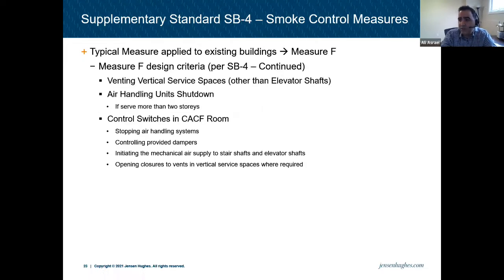So this is basically measure F. Other requirements: if you have other shafts or other vertical service spaces, you may have to pressurize those. Air handling unit shutdown: if there are more than 2 stories, again, you need to shut it down. And it comes to the last requirement, the switches that you need in your CACF room. So you need to control all those fans and the air handling system. If there is a damper provided, you need to have a control for that damper. And for the opening and closure of any vent in a vertical service space that is provided, you have to have a switch for it, so mechanically you can open and close them.